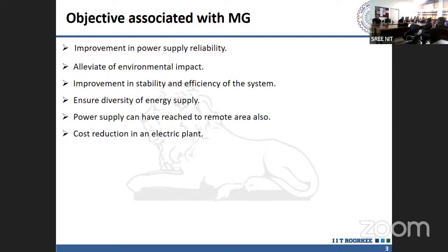Now, once we try to cater to all this load locally, what was happening previously? This whole impact was appearing on the generating plants. Whenever there are inter-area oscillations which finally lead to instability, they are going to be reduced, because locally we have now created sources and loads which are supplying here. So the major stability problems coming into the power system, that probability is reduced.